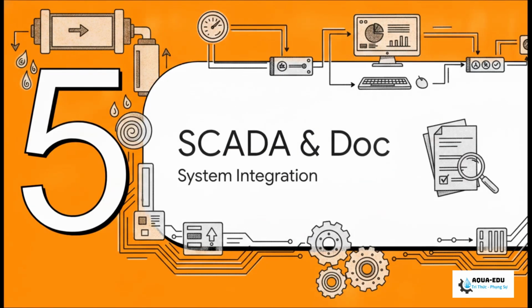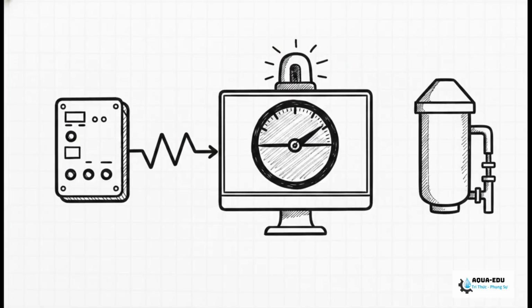Let's move into Phase 5, SCADA and documentation. Out in the field, you need to verify that the 4 to 20 milliamp loop actually matches the SCADA display in the control room. For example, if your range is minus 1,000 to plus 1,000 millivolts, a 0 millivolt reading should output exactly 12 milliamps. Next, make sure you firmly set your SCADA high alarm. Typically, we put this at plus 250 millivolts. If that alarm triggers, it's instantly warning us of a chlorine breakthrough. That means a technician needs to immediately get out there and check the carbon filter or the SMBS dosing pump.